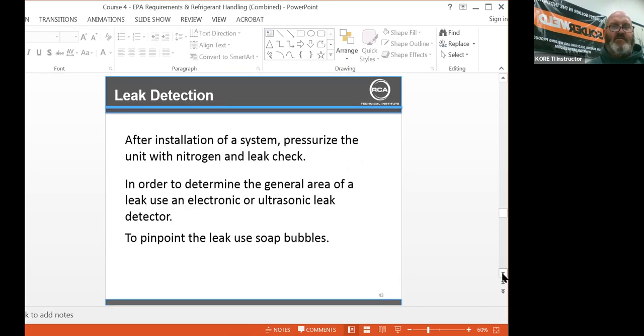Leak detection after installation of the system. Pressurize the unit with nitrogen and leak check. In order to determine the general area of a leak, use an electronic or ultrasonic leak detector. To pinpoint the leak, use soap bubbles.